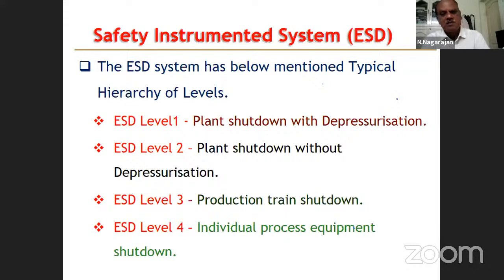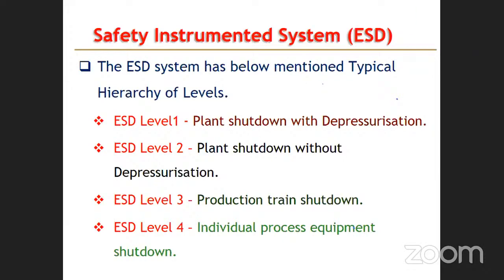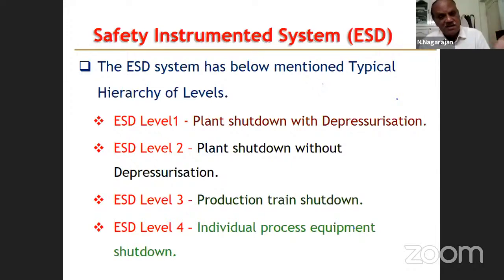ESD level 2 is a plant shutdown without depressurization. The type of upset or hazard is not that serious, so you can just shut down the plant, isolate the equipment, and keep them in the pressurized condition. So when the problem is solved, you can start the plant without any problem. If you totally depressurize, again commissioning of the plant has to happen. That will take some time, so it is loss of production. So only when there are the most serious emergency conditions, ESD level 1 will be activated.